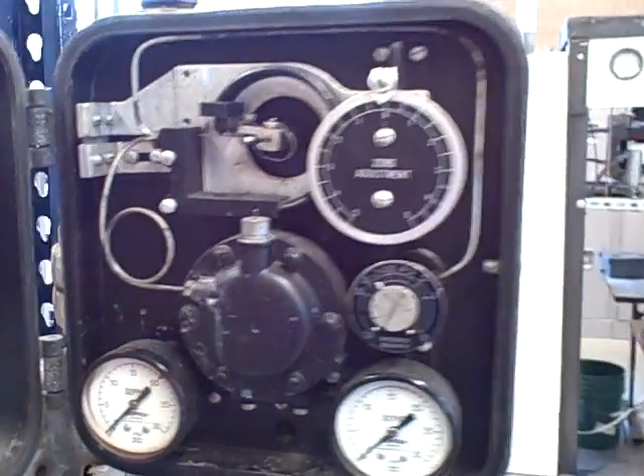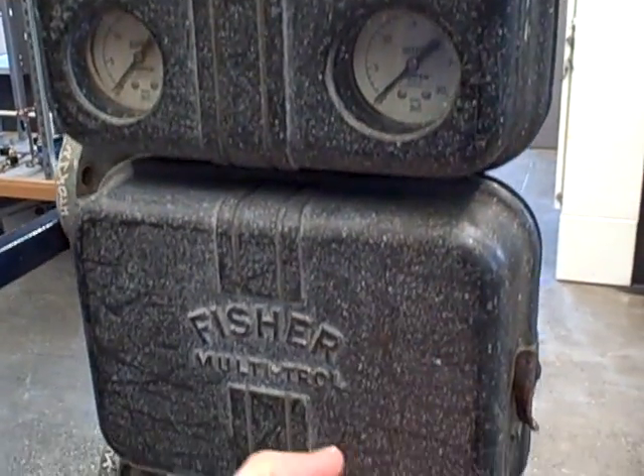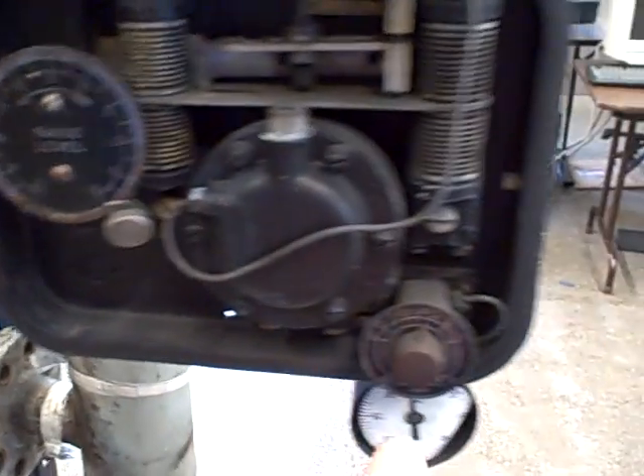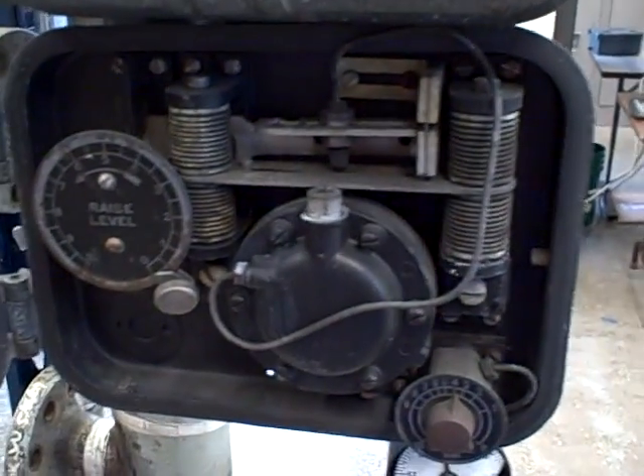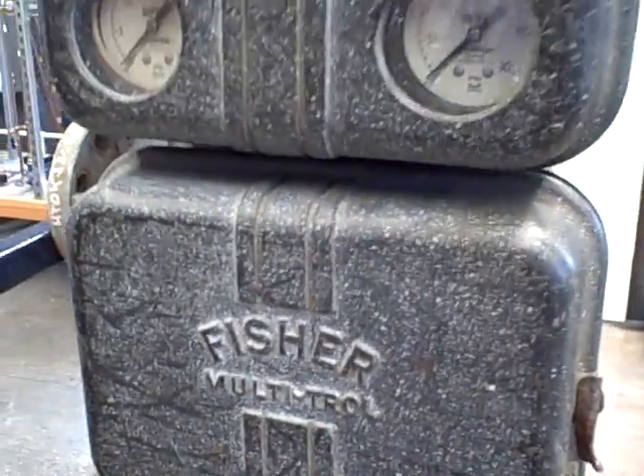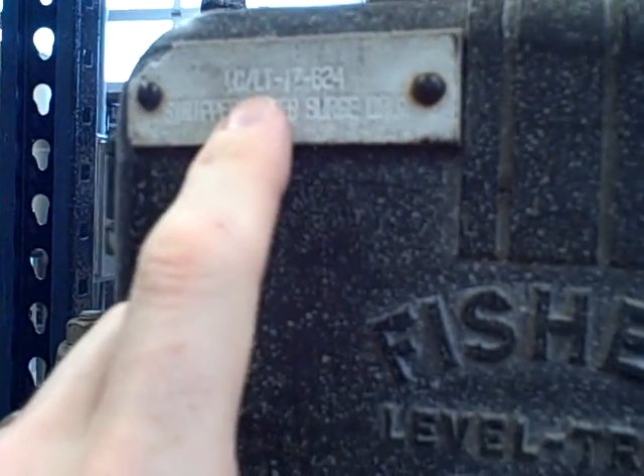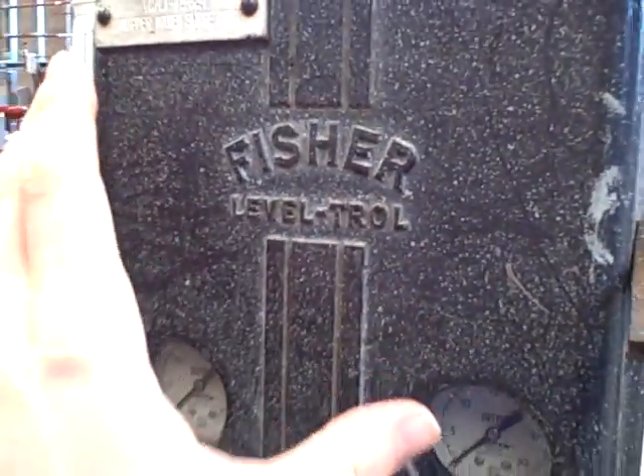That is a Fisher Leveltrol level instrument. This particular model is attached to a Multi-Trol, which is a proportional controller. This is the set point adjustment, here's the proportional band, and this is a motion balance mechanism for proportional loop control. This instrument was designed to control a control valve to control water level — in this case it was on a stripper vessel. It says right here: stripper water surge drum LT 17-624. This was a level transmitter for that surge drum level and a level controller as well, on the same unit.